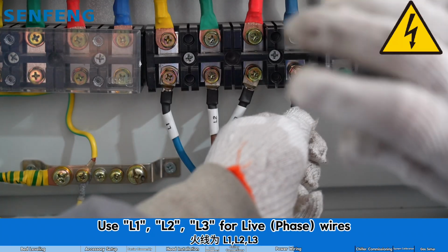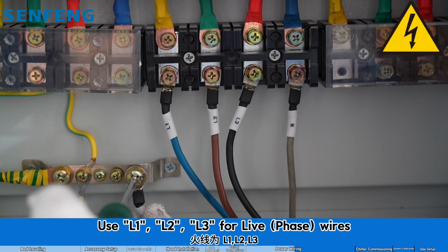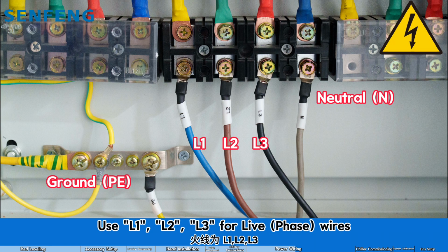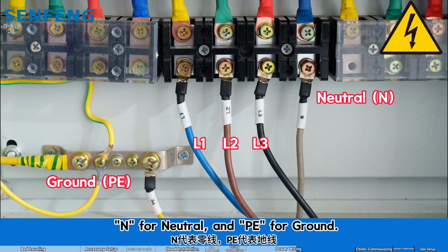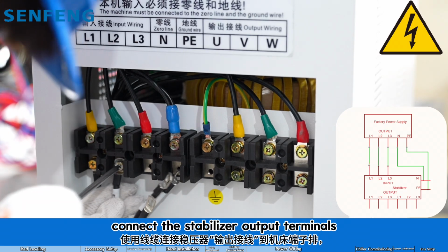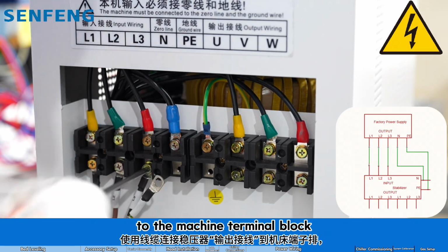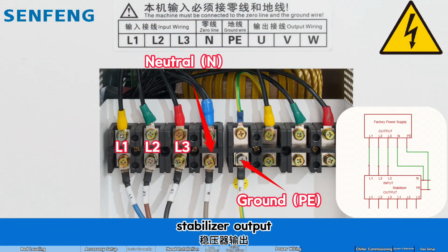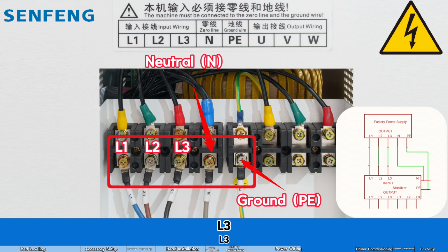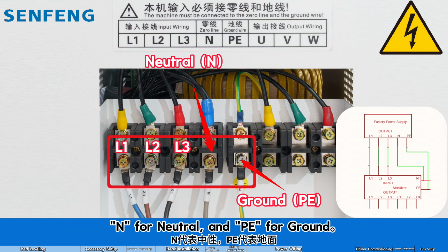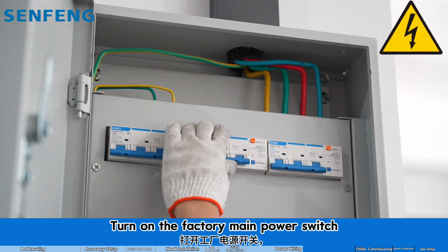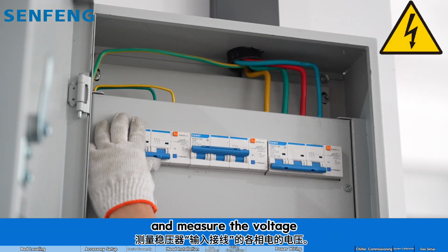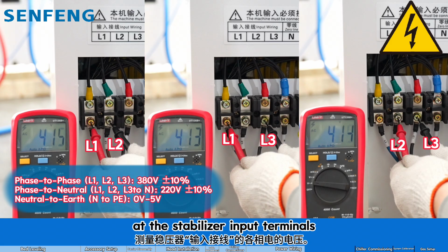Use L1, L2, L3 for live, phase wires, N for neutral, and PE for ground. Connect the stabilizer output terminals to the machine terminal block. Stabilizer output L1, L2, L3 for live, phase wires, N for neutral, and PE for ground. Turn on the factory main power switch and measure the voltage at the stabilizer input terminals.